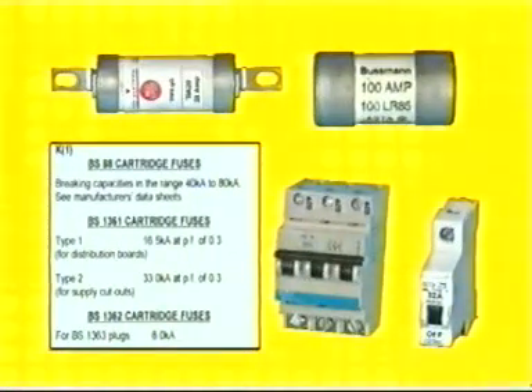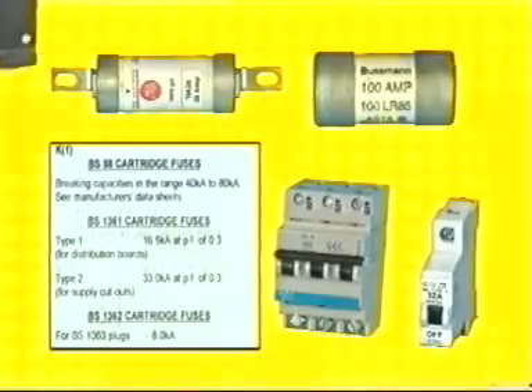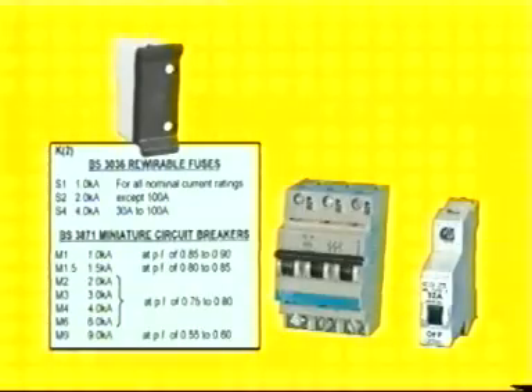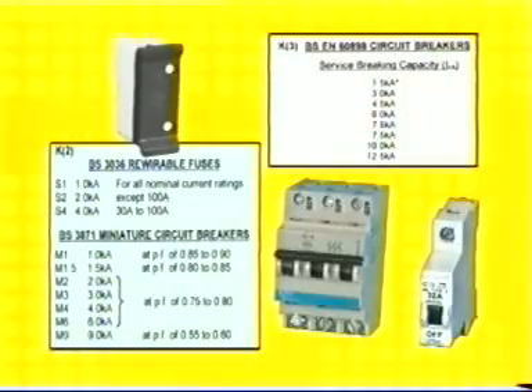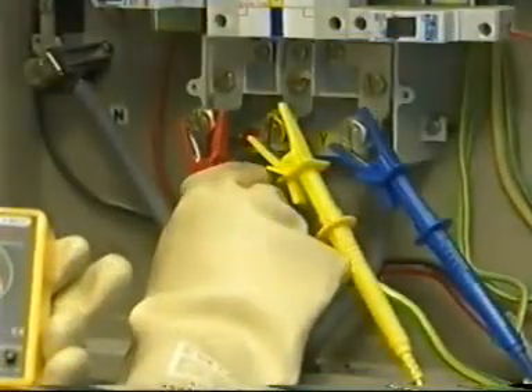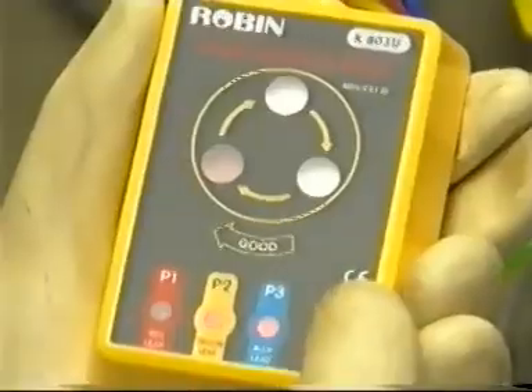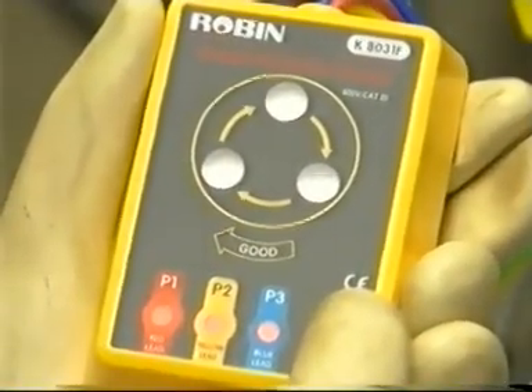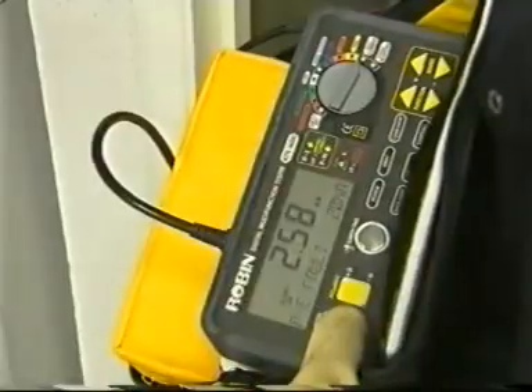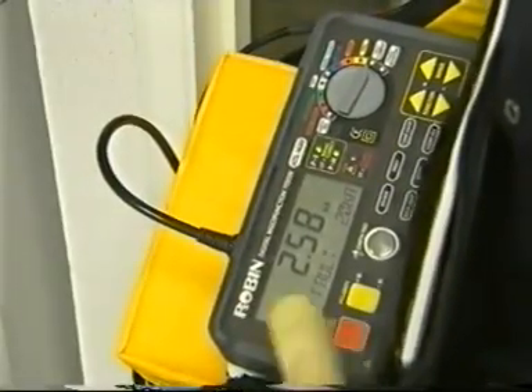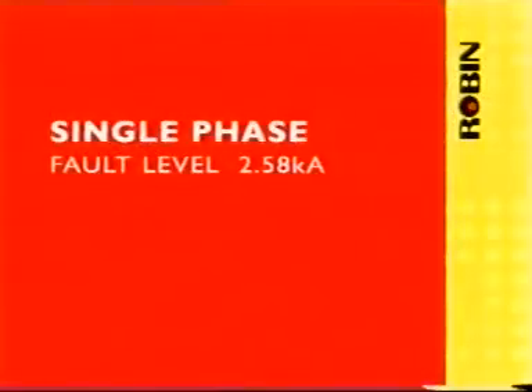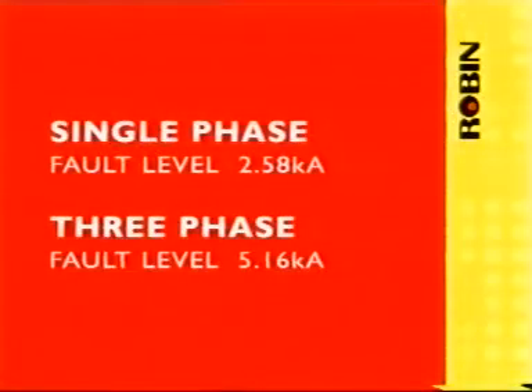Fuses and overcurrent circuit breakers have a declared limit to their capability of breaking and, in the case of circuit breakers, making a fault current. Their limited breaking capacity must not be exceeded. Tests for polarity and correct rotation of three-phase supplies should be performed where appropriate. Electrical tests may be conducted to determine fault levels at distribution boards and consumer units where protective devices are fitted. As an approximation, single-phase short-circuit current values may be doubled to assess three-phase conditions.